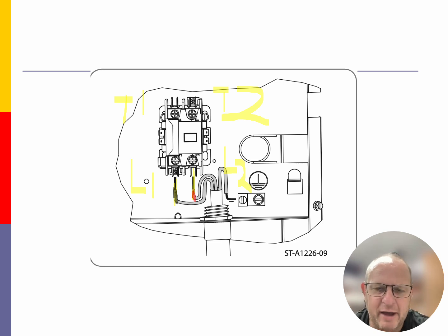But it really doesn't matter the colors, because we're just bringing in two hot legs into the outdoor unit. And make sure that you check your nomenclature plate to find out what your voltage actually should be for that unit before hooking it up. Remember, furnaces are 120. Outdoor units are typically 240 volt systems. Electric furnaces and air handlers are 240 volt as well.